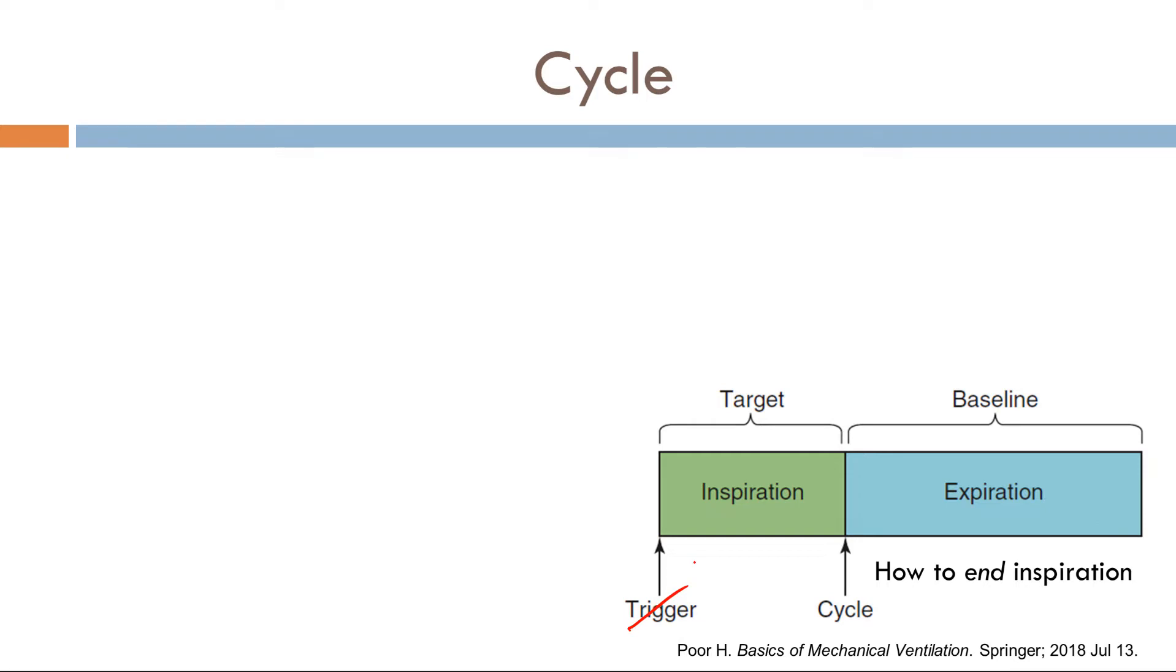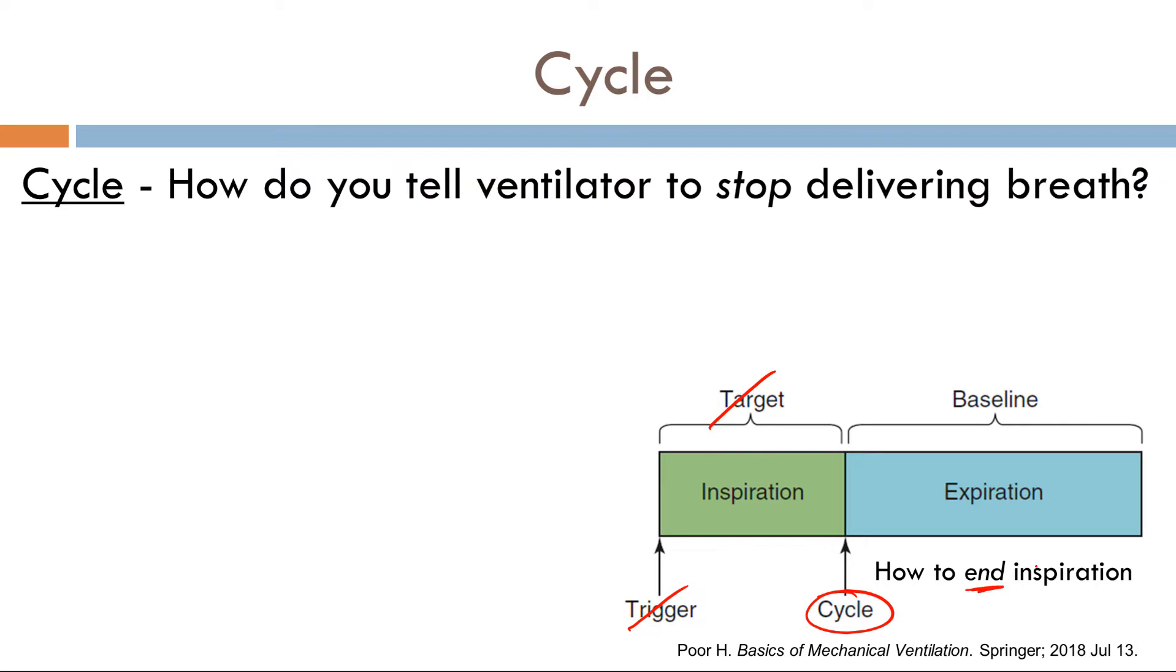So we've talked about the trigger, we've talked about the target, now it's time to talk about cycle. Cycle is how to end inspiration. So how do you tell a ventilator to stop delivering a breath? A breath would continue indefinitely in a ventilator unless a particular variable told it to stop delivering your breath. What's that variable? That's the cycle variable. Now what are your cycle variables? You have volume cycle, time cycle, pressure cycle, and flow cycle.